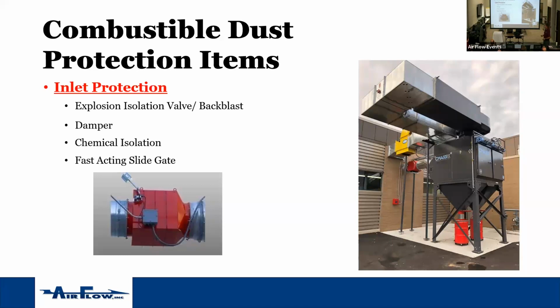For your inlet protection, this is an EIV, explosion isolation valve. What it does is it stops the back pressure and closes off as that back pressure comes through to stop the flame ball from going back into the space. It's probably the most cost-effective way to stop it. And it only applies for certain KSTs on here. So when you get into a KST above 300, I believe, an EIV won't work. You'll have to get into some other type of device, whether chemical or a fast-acting slide gate. Chemical isolation is another one, and fast-acting slide gate.